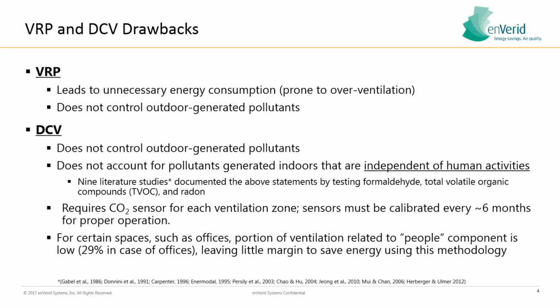It also doesn't account for pollutants generated indoors that are independent of human activities. So there are many literature documents, many studies, that indicate that formaldehyde, TVOCs, and radon are not addressed by demand control ventilation. They also require CO2 sensors for each ventilation zone. Those sensors must be calibrated frequently. That calibration metric is actually changing in 2019 ASHRAE as well, so we'll talk about that. But you have to calibrate those sensors. That's expensive. That's a big-time maintenance item for facilities teams. And then for certain spaces such as offices, the portion of ventilation related to the people component is low. So that leaves you very little margin to save energy using demand control ventilation in many cases.